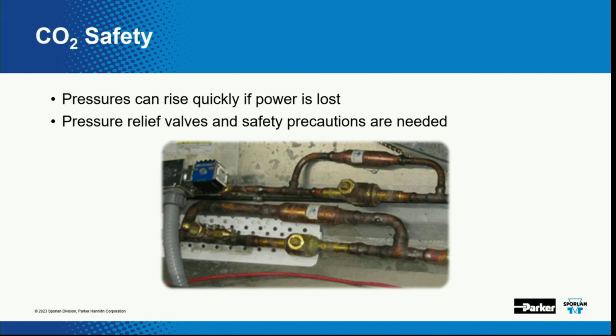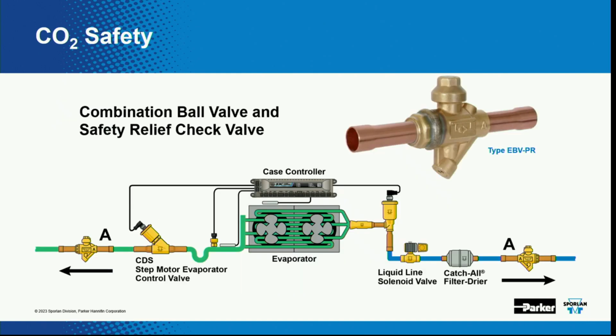Like in this case, what I'm showing here is a check valve being routed around an isolation valve. And that's so that the components downstream of that, if the system's warming up, it's allowed to vent the refrigerant, the CO2, out beyond or around that isolation valve. Otherwise, something's going to pop. High pressure.